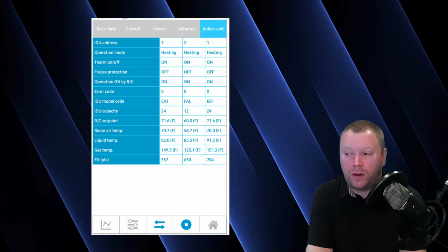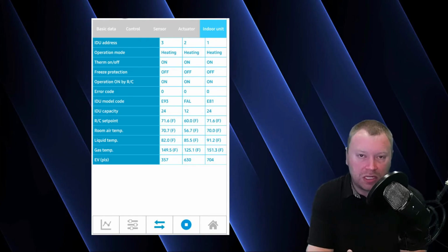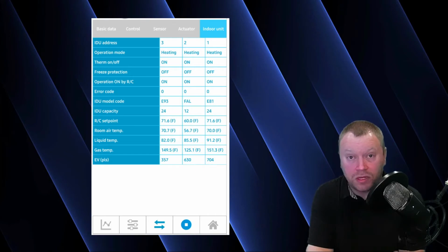But if we were to base everything on this one snapshot, I would say that my system was not performing very well. I like to use data like this because this shows us what something could be doing in one instance, but what it should be doing in most instances. I want to show you data that isn't perfect so that you can see where the room for improvement needs to be. The reason I like to talk about this type of data is it's not horrible, but it's also not perfect. And so this gives us the opportunity to discuss what things should be doing in the next couple of screenshots. And then as you sit there and keep taking your runtime, knowing what it should be doing allows you to then watch it and make sure it responds accordingly.